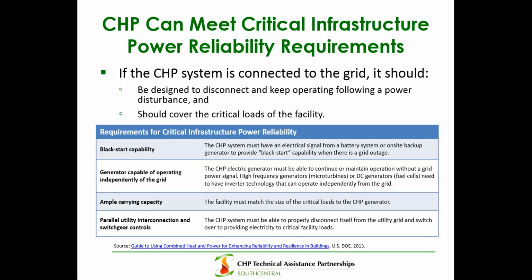One key thing to keep in mind when designing and installing a CHP system, whether talking to an engineering company, an ESCO, or just contemplating CHP, is to make sure it has the right components. We've seen cases where it's not properly configured, so it can't operate when the power goes down. It essentially has to shut off because it doesn't have the right interconnection with the grid.